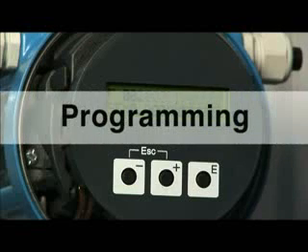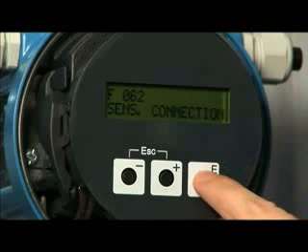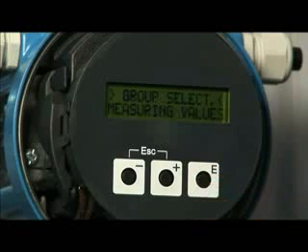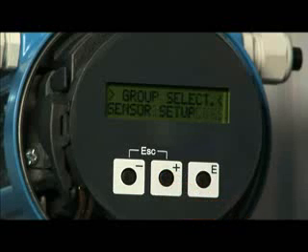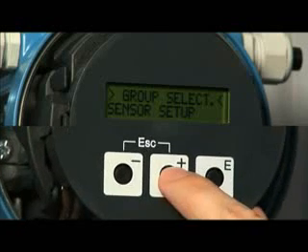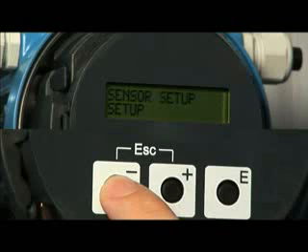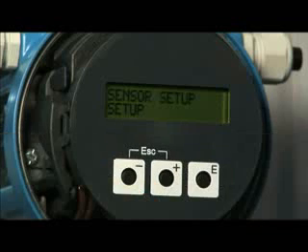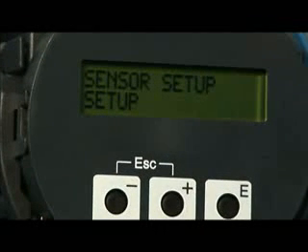Begin the programming of the prosonic flow meter by pushing the E button. This button is used to initiate the programming sequence and later for confirming selections. The plus and minus buttons are used to access the various selection options. After entering into programming, select Quick Setup or Sensor Setup.